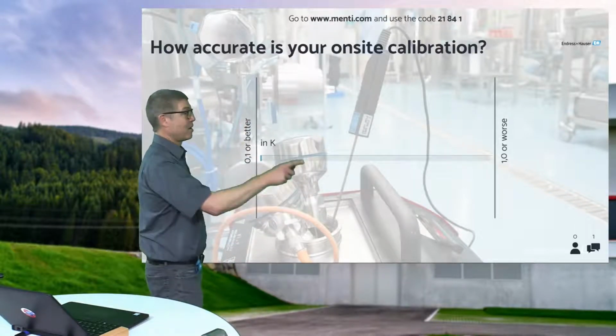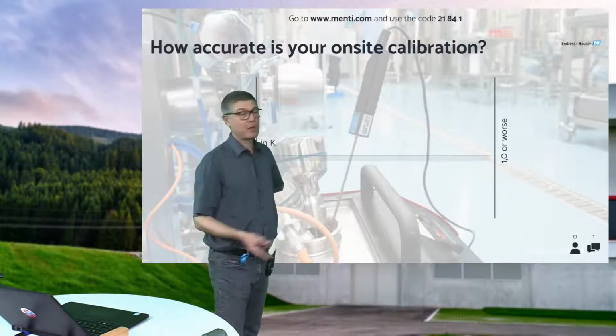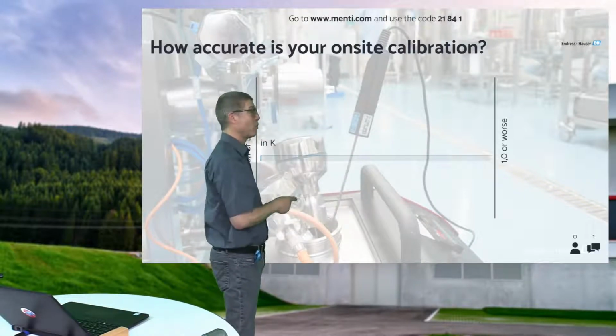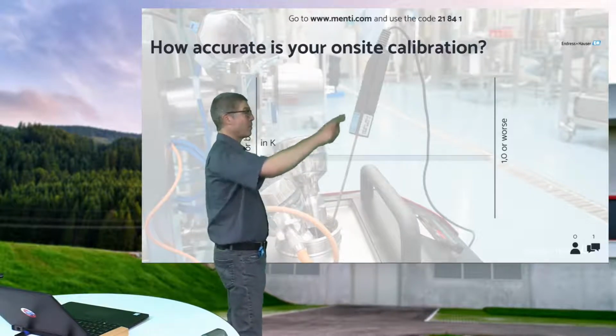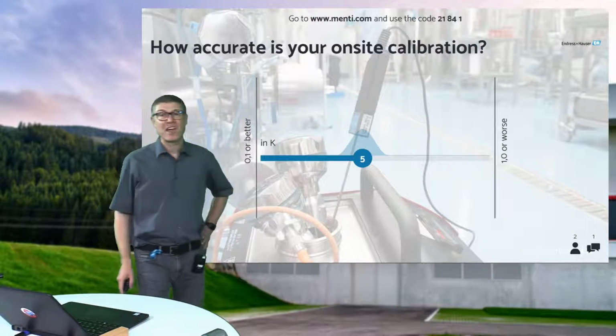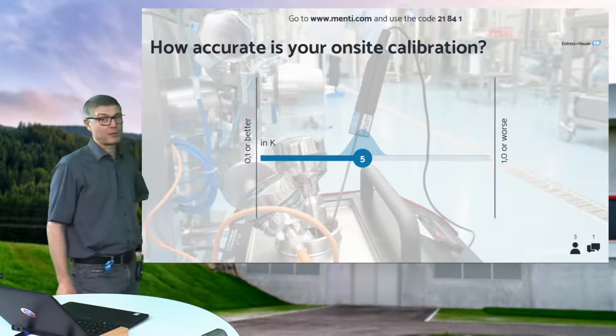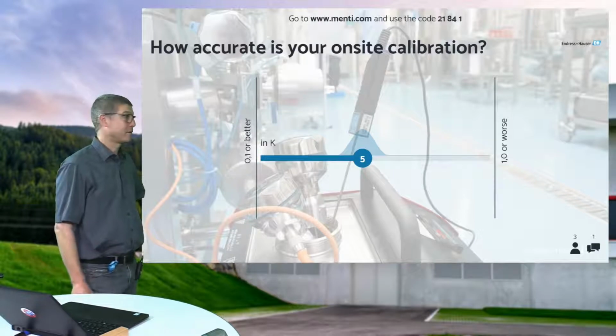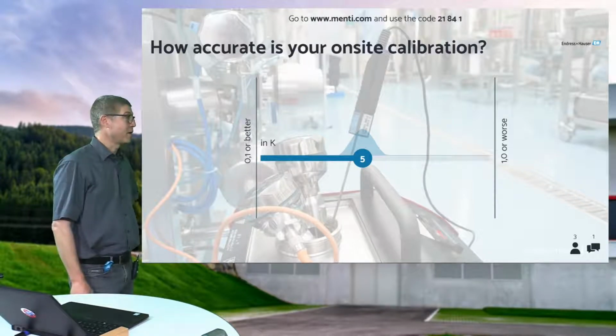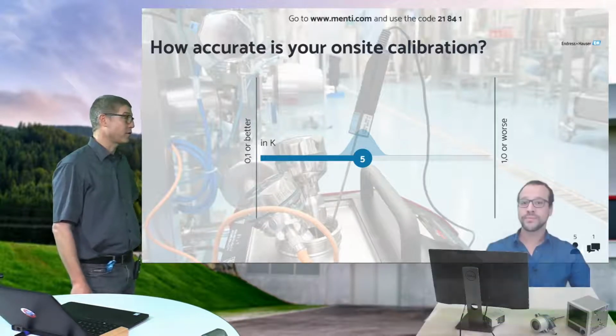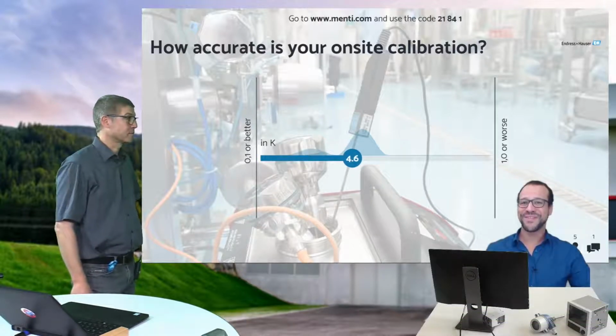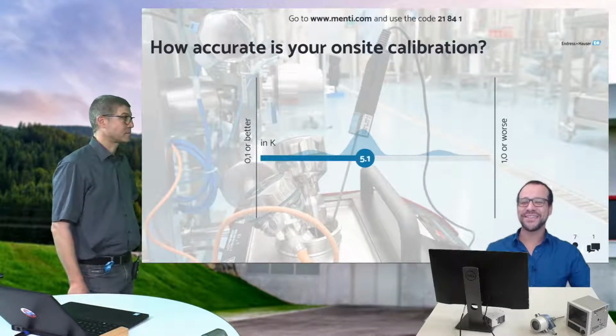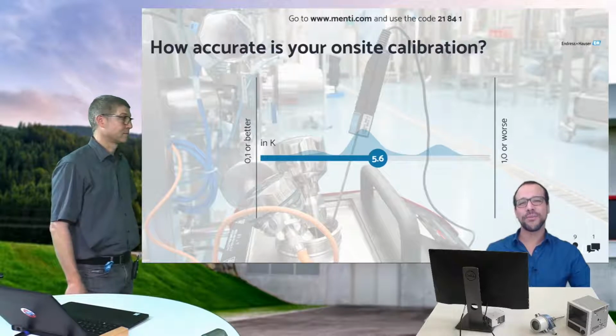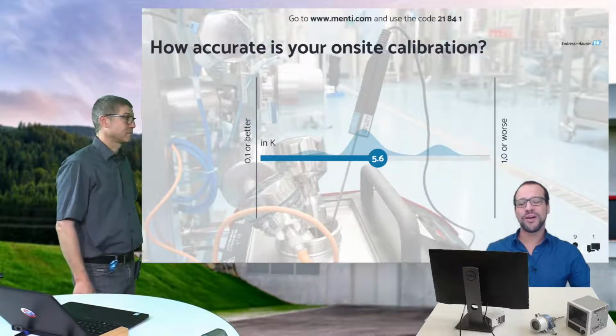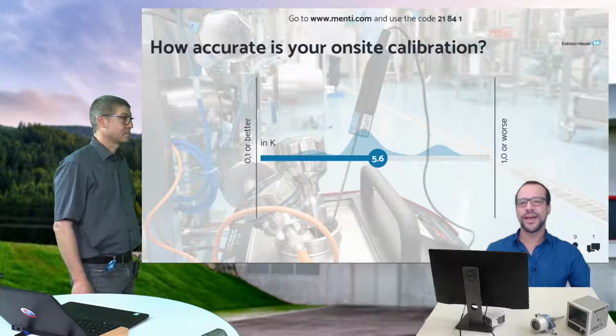If you take a dry block calibrator, which is the majority of the applications, if you have your reference, if your device is under test, how accurate do you think you can be? This would be very interesting for me to see your answers to this. So we have a scale from 0.1 to 1 degree or worse. So, final sprint. Please give us one last feedback on that and let us know what you think, how accurate you might be. And I think that might be one of our aha moments when we come to the next slide showing what the accuracies of those on-site calibrations regularly are.